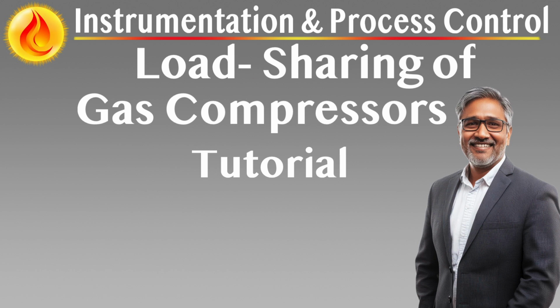Functional logic and architecture. Real-time surge deviation monitoring. Each compressor's anti-surge controller continuously calculates a value representing how close the machine is to its individual surge control line. This deviation, often referred to as dev, becomes the primary input for the load balancing algorithm. Zero dev, compressor is operating precisely on its surge line. Negative dev, compressor is dangerously close to surge. Positive dev, compressor is operating safely away from surge.